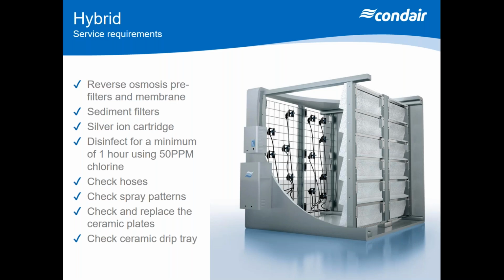But what you're going to need to be doing also is cleaning these ceramic plates down as well to make sure they're being kept clean, because obviously they can also act as a filter. So it's worth just making sure they're being kept clean. Wipe them down. If there's anything that's cracked, it's also worth just changing those out. But it's very similar to the way the high pressure system works in terms of the requirements for a hybrid system. So you need 2 disinfections a year.